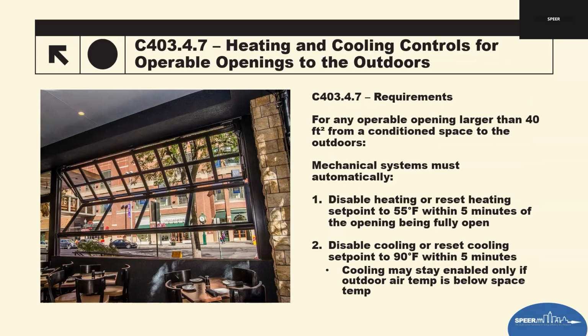We've talked about this one on several things in the past, but they continue to keep addressing this slightly and moving it around and adjusting what their requirement is. But one of the biggest sources of wasted energy is large overhead doors or roll-up doors. So basically they have now strengthened the requirement for automated HVAC responses when these things happen. So the code requires now, when an operable opening larger than 40 square feet, it used to just say roll-up doors, now it says 40 square feet or larger, is fully open, the HVAC system must automatically take action within 5 minutes. Before it just said must take action. They added the 5 minutes to it.